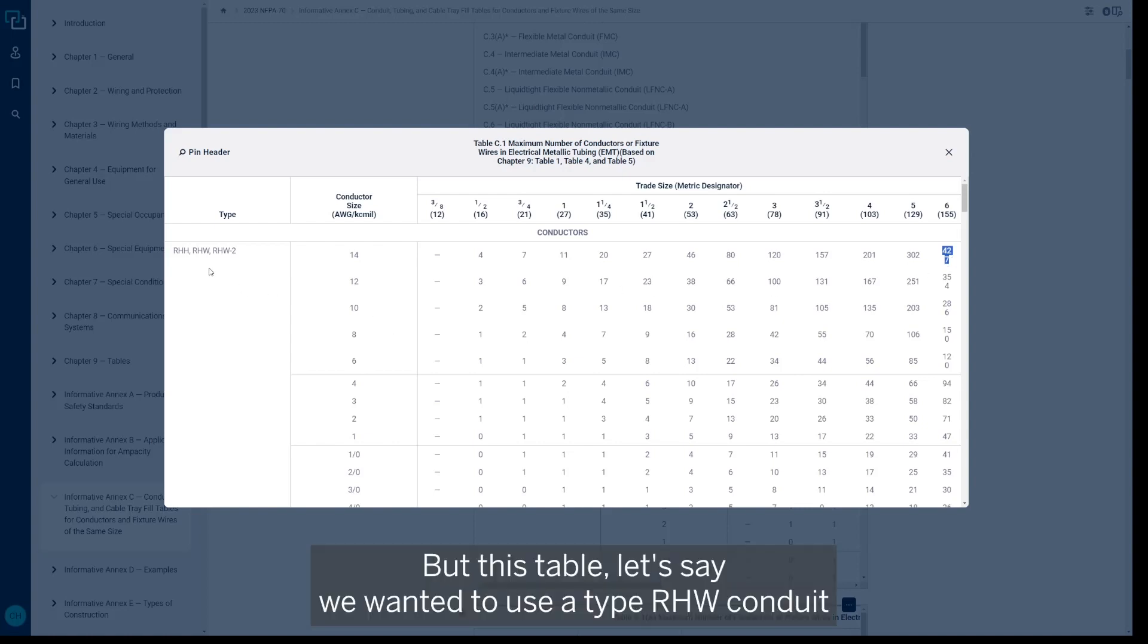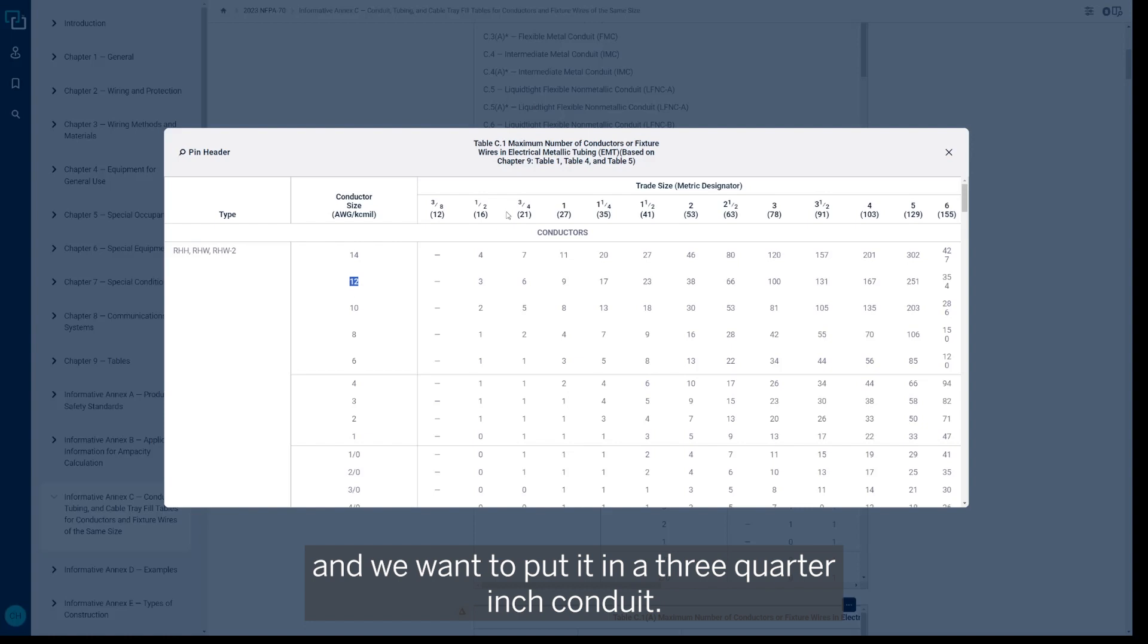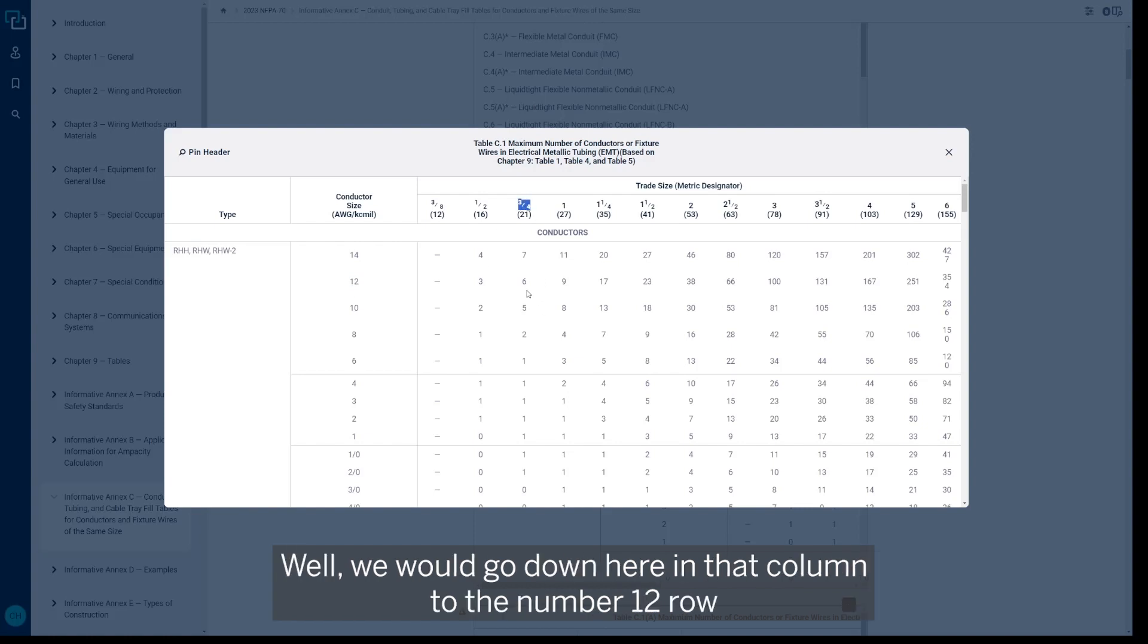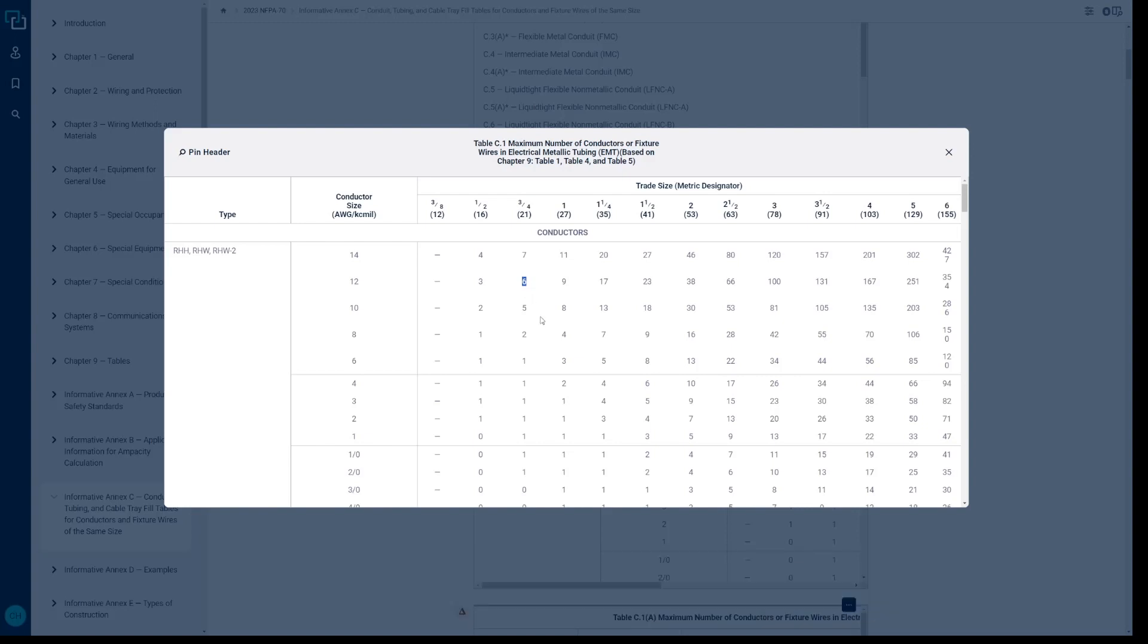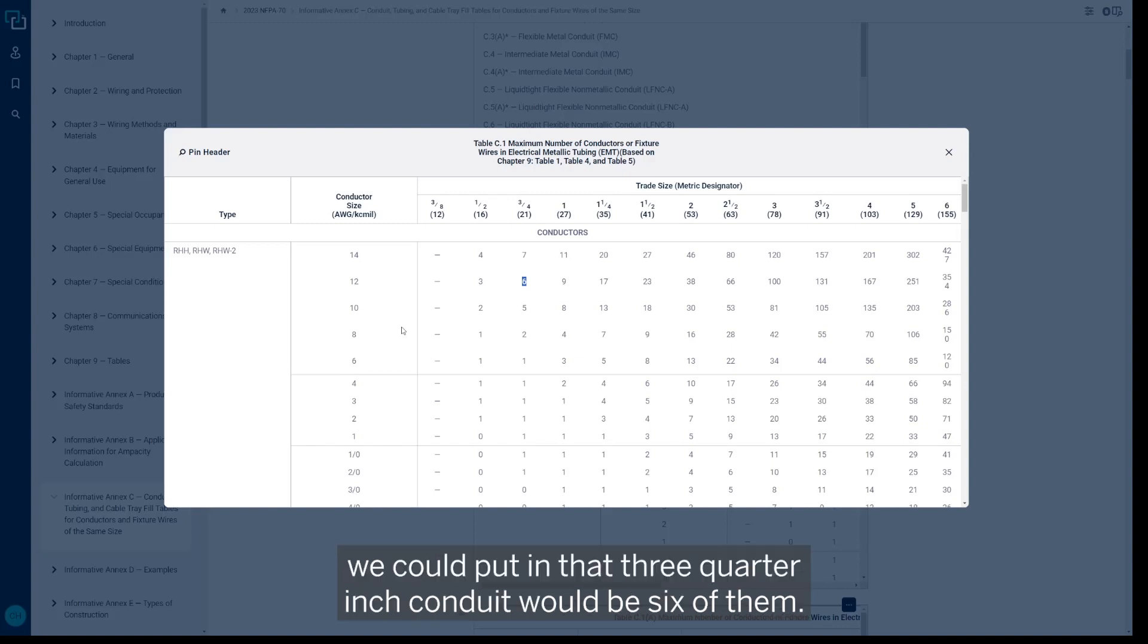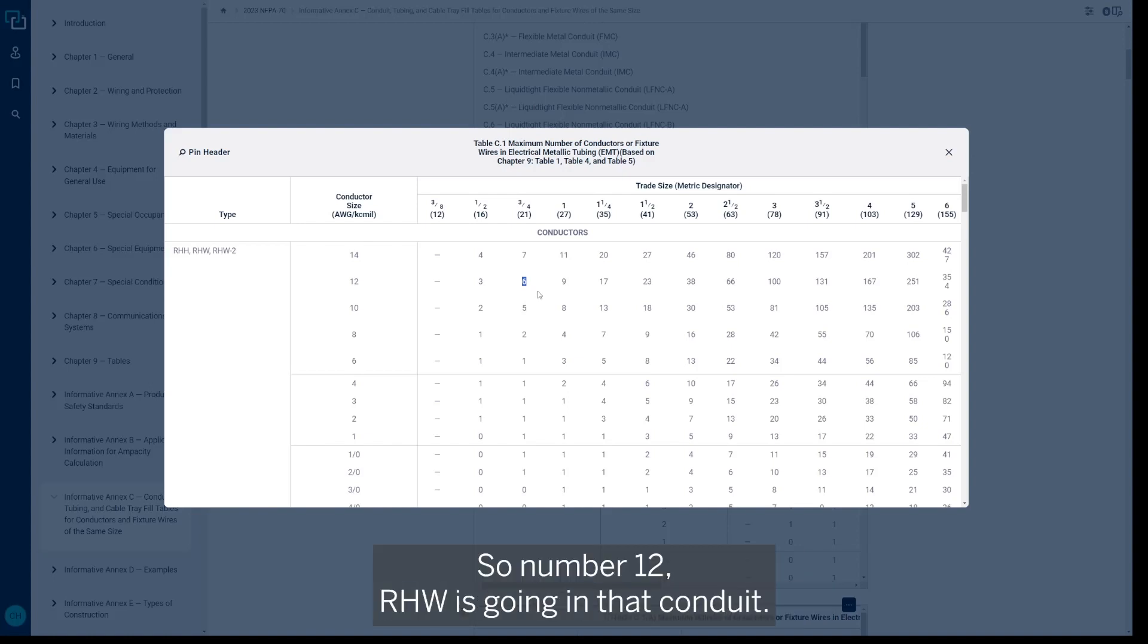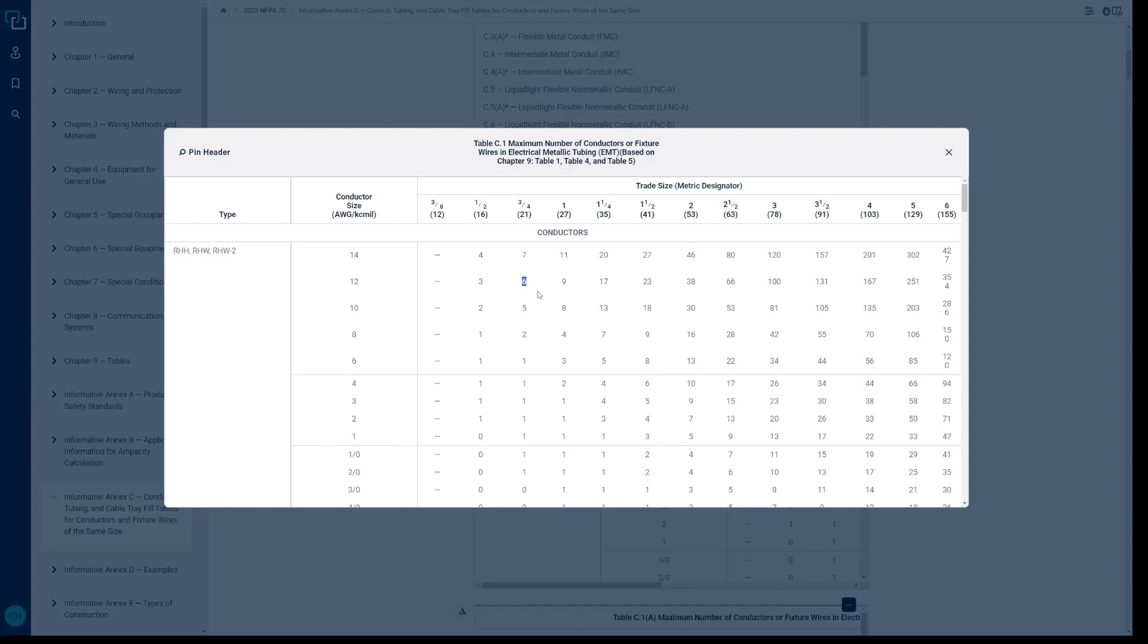But this table—let's say we wanted to use a type RHW wire, number 12, and we want to put it in a three-quarter inch conduit. Well we would go down here in that column to the number 12 row, and we can see if we're using the number 12 RHW, the maximum amount we could put in that three-quarter inch conduit would be six of them.